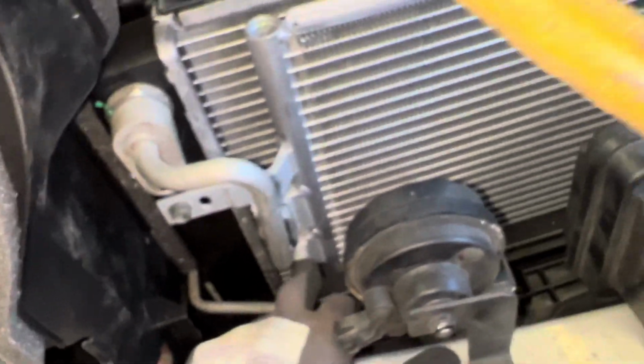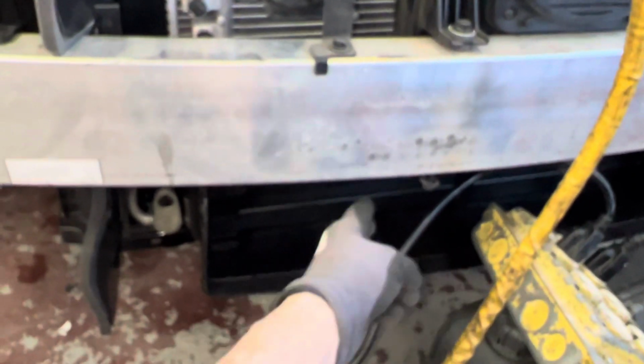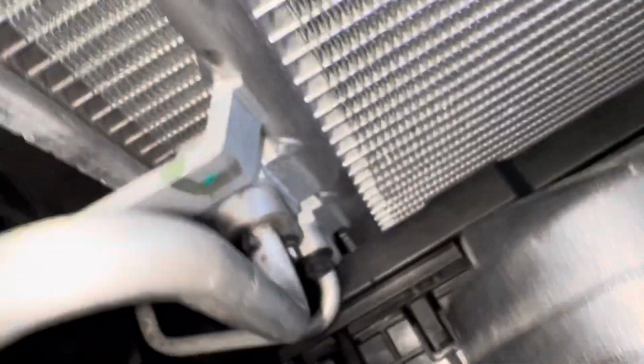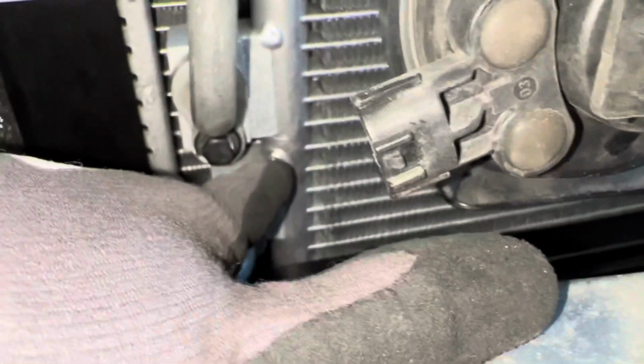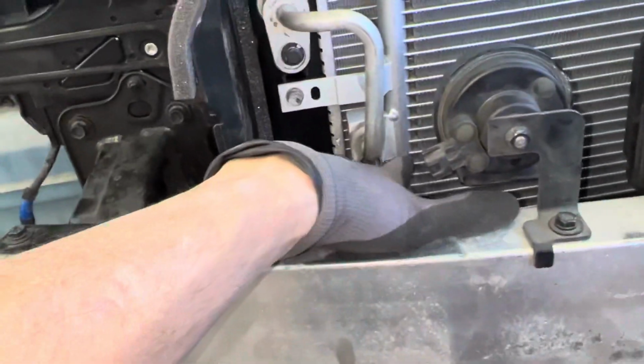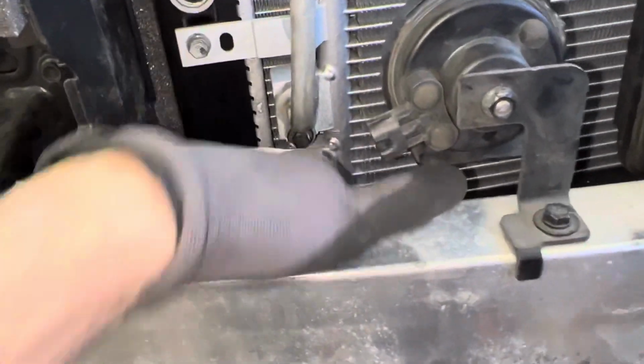Okay, because that looks like an unusually high placement for subcooled liquid, because the condenser goes down to here, but its liquid line discharges way up here, and that's higher than the 4, 5, or 6 parallel tube runs at the bottom of the condenser where they usually run. Trying to see down there. And actually what I need is the old condenser to look at it. I need to cut up the old condenser. I wish it was right here and I had my little bandsaw, I'd cut it in half and divide the header tubes up in half so we could see where the passages and the separations are. It's like you could see right here, there's a little separation. You see that little disc? You see that little line? That's the separation separating this part of the condenser from below from that part of the condenser.